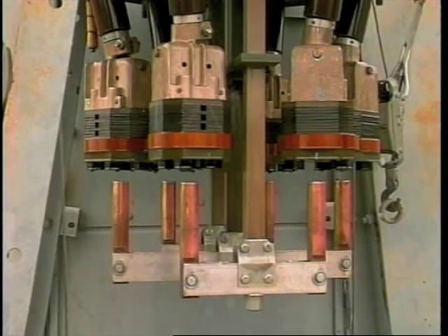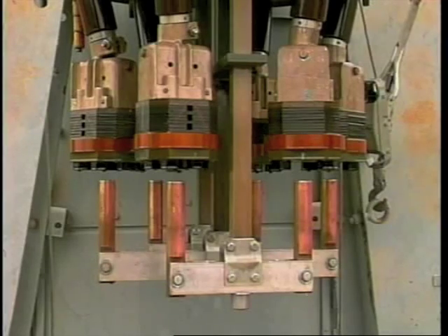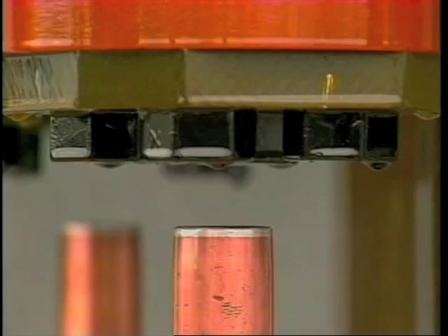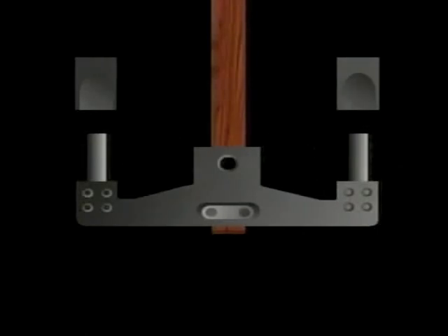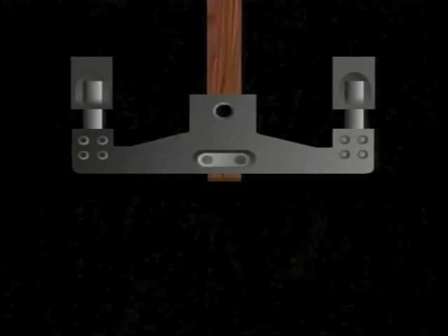Some oil filled circuit breakers use bayonet type contacts. These provide good surface contact with longer service life than standard butt contacts. The contacts consist of a rod which serves as the moving contact. The rod fits into a circular cluster of stationary contact fingers. The tips of the moving rod and stationary cluster serve as arcing contacts. They are made of harder, less conductive material than the main portion of the contacts. The contacts must be properly aligned, adjusted and maintained in order for the breaker to carry normal load current without thermally damaging itself.